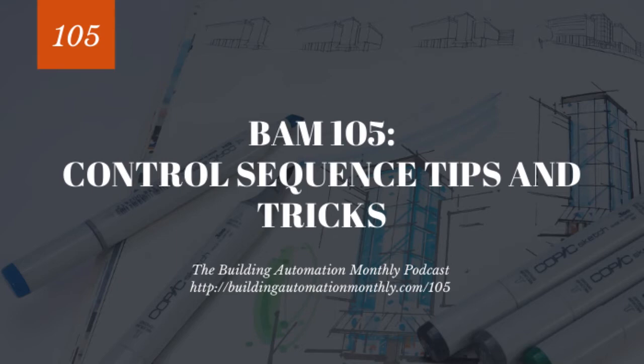Now, why would you want to rearrange things? Well, the reason you want to rearrange things is that you want to do two things. One is you want to make it easy for the programmer, or easy for yourself if you are the programmer. So that's one reason. But the other reason is, let's say you go with a commissioning agent, and the current way that the sequence is arranged, it's not going to work. It's just not going to work. So for example, the chiller enables before the isolation valves turn on, and you've got an issue there because that chiller is looking for flow.